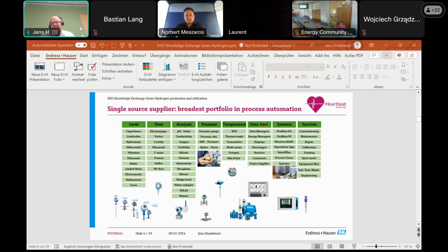The benefit is that especially for critical applications, which you also have in green hydrogen, where you have functional safety, explosion proof, or if you simply want to show that the device in your flow device is working like at the beginning, this verification is used. We also have a certificate from TÜV, which is a certification body. So long story short, especially in remote applications, where electrolyzers will be put somewhere on the planet, this is a good possibility besides permanent process and device diagnosis, to check now if this flow device or level device in a critical or important application is working.